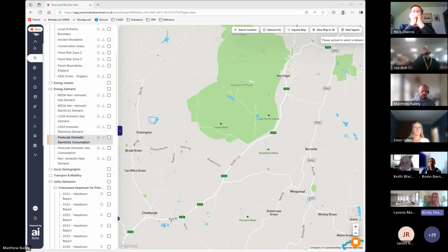Okay, so on the solar farm example, then could you look at the network cabling and the local substation and think that could work as a connection? Like you can see the 11 kV line going through a field or whatever. Could you use it for that? Yeah, you could use it for that. I mean, you'd probably have a better idea of the land use than we would if it's the local area, but just try and visualize, we'd need to put a cable somewhere to connect your asset to our network. Where's that cable going to go? If it's going through a river, that's going to be complicated and expensive. If it's 5 meters under a bit of field that no one uses, that should be pretty easy.